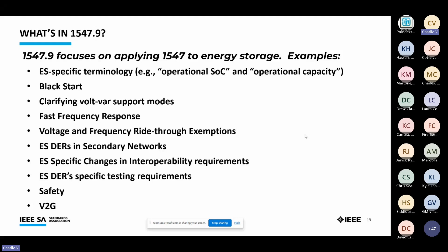To make it simple, 1547.9 follows the clause or chapter order and topics of 1547-2018. The one exception is clause 12, added on safety, which Chris co-led. IEEE standards are not safety standards - that's the realm of NEC, NESC, and the safety and fire safety communities Chris works within. But with the issues of prime mover batteries having unique safety attributes very different from other prime movers, that chapter points to the appropriate safety codes that designers, deployers, and connectors of these assets should be aware of.